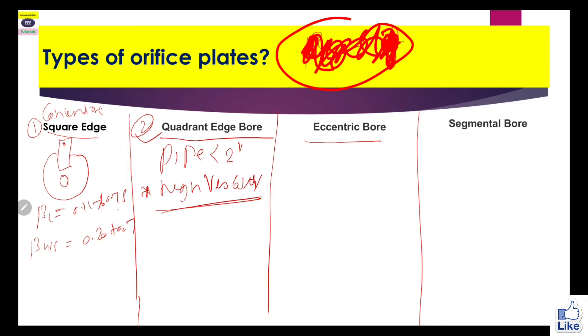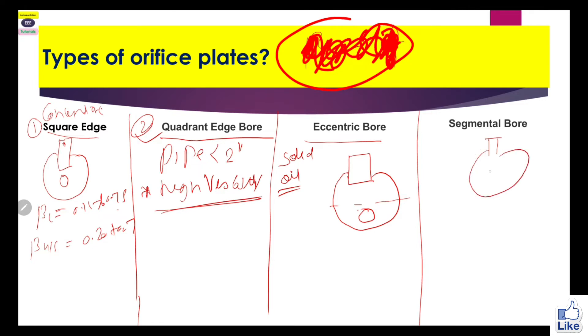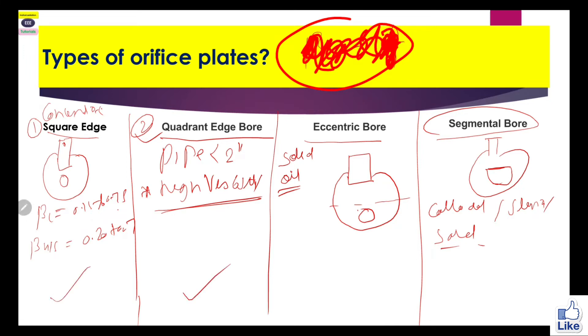Eccentric bore is also very important. In the eccentric bore, the middle line is visible and the hole is positioned below that middle line. The application of eccentric bore: whenever solid or oily material is present in any fluid, the eccentric type orifice plate can be used and it will work effectively. For segmental type, the bore construction looks like a segment. It is used whenever your fluid is colloidal, slurry, or may contain solids. So these are the four types of orifice plate generally used.